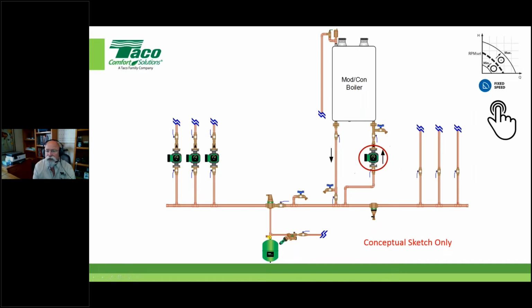So we'll focus on this circulator. I will say this while we're on this slide: remember these ECMs have all kinds of modes of operation. Well, the only thing that makes sense in this near-boiler pump application is that 0 to 10 or 4 to 20 milliamp, or there are some other things being done, pulse width modulation and others. One way or another, if you have that control, fine. But if you don't, there's only one other mode that makes sense, and most every ECM has it, and it's called fixed speed. Some people call it constant speed. But what we're saying is there's nothing within this circuitry. If you look at it, there's a boiler's heat exchanger, there's some piping, there's a T here, that's the circuitry that this circulator is responsible for.